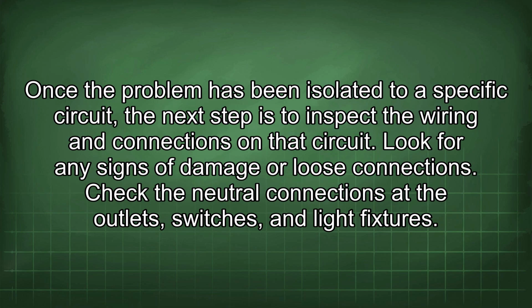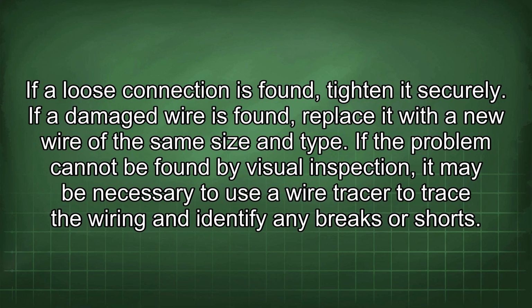If a lost neutral is suspected, the next step is to isolate the problem. This can be done by turning off circuit breakers one at a time and observing the voltage readings. If the voltage returns to normal when a particular circuit breaker is turned off, it indicates that the problem is on that circuit. Once the problem has been isolated to a specific circuit, the next step is to inspect the wiring and connections on that circuit.